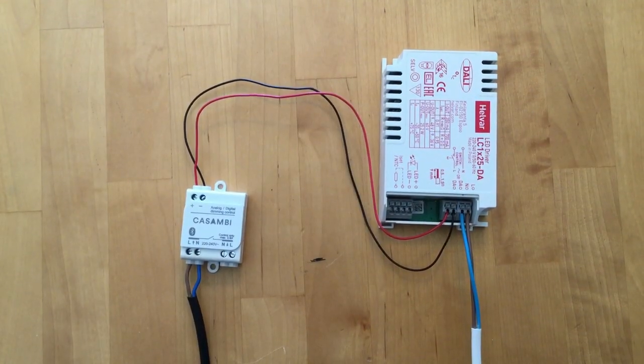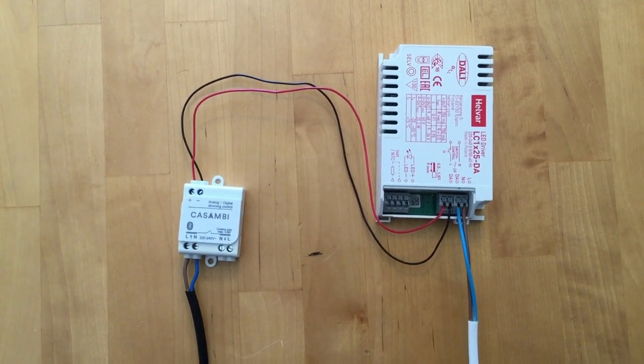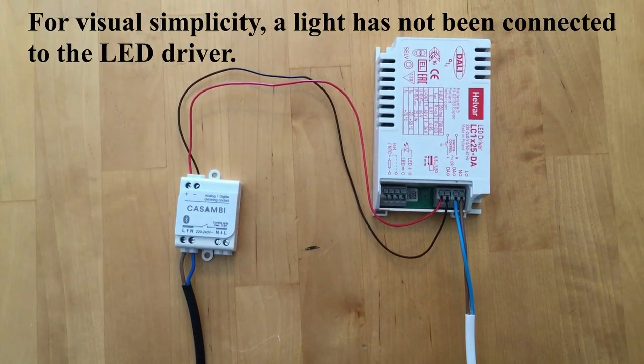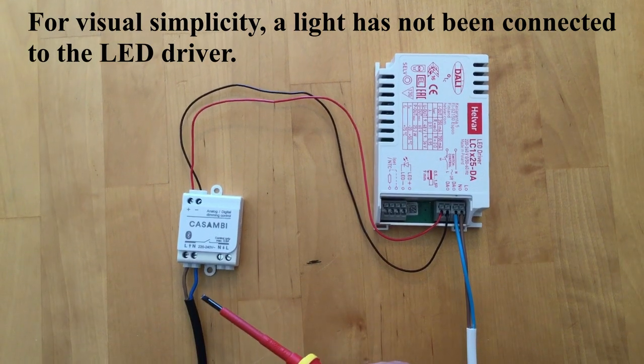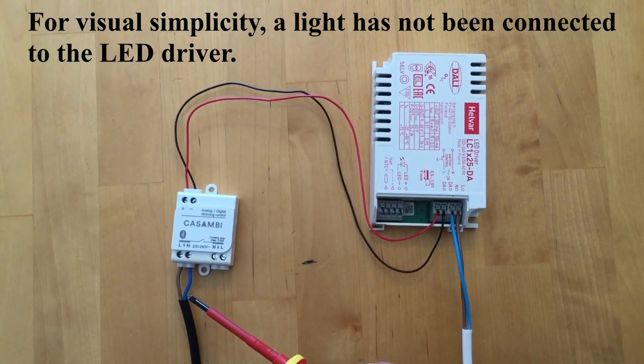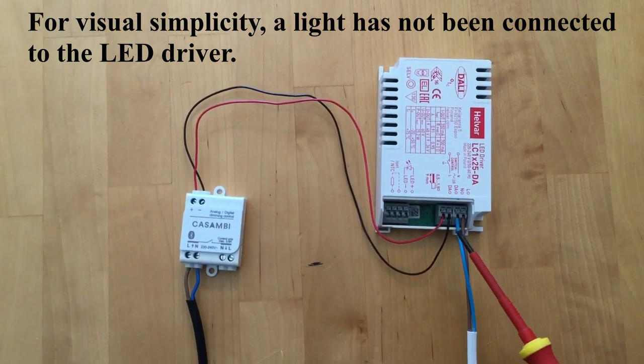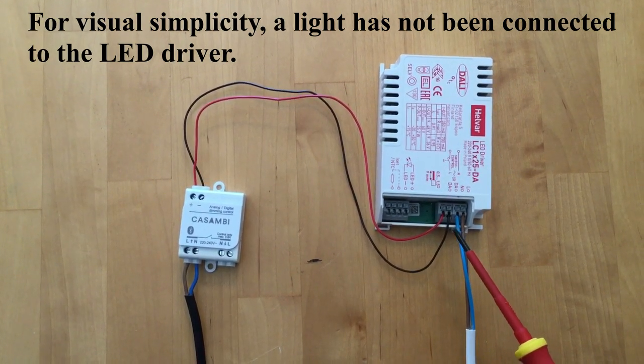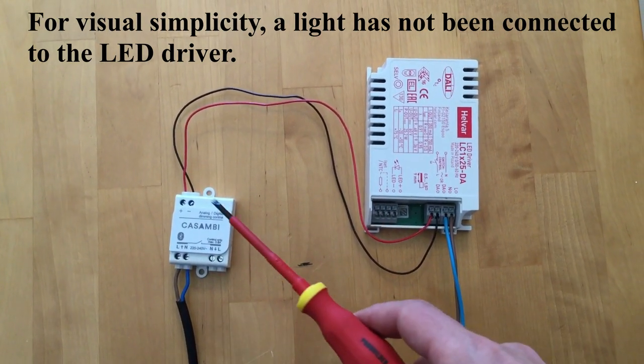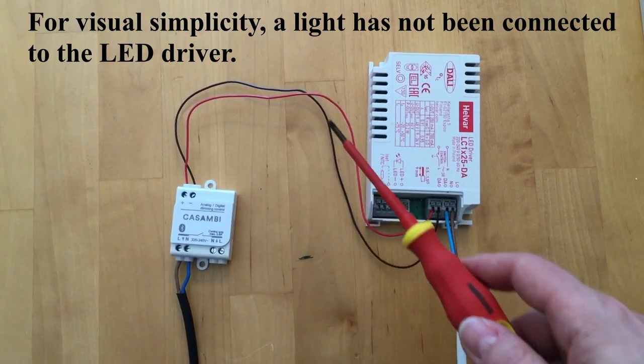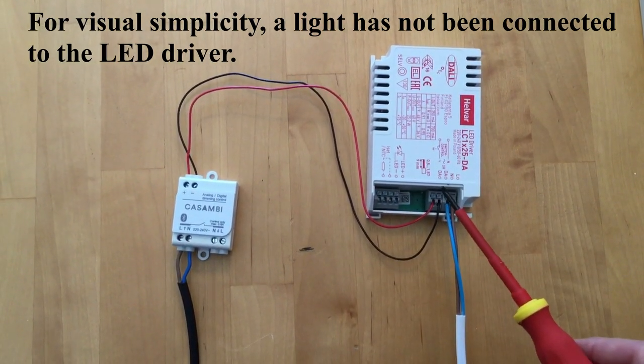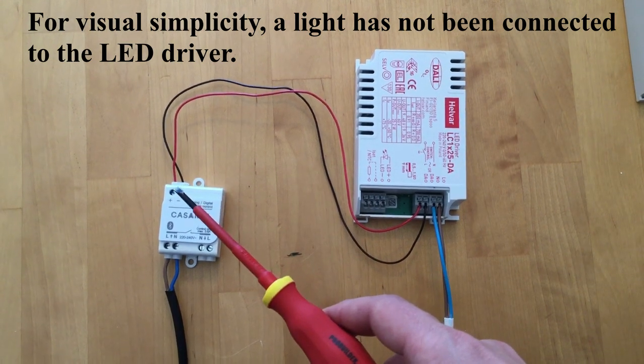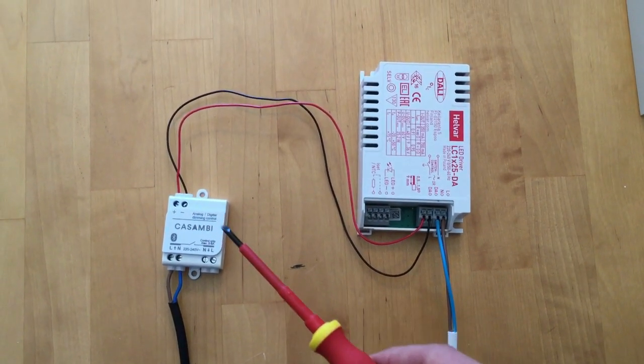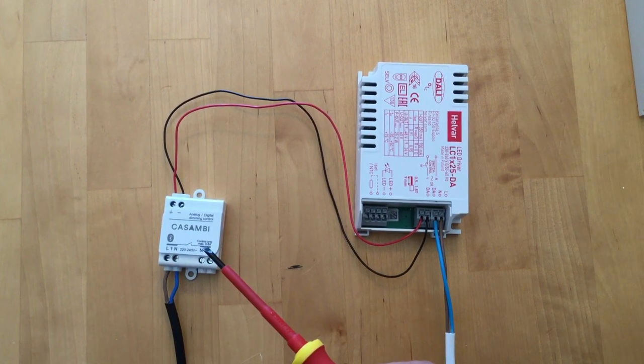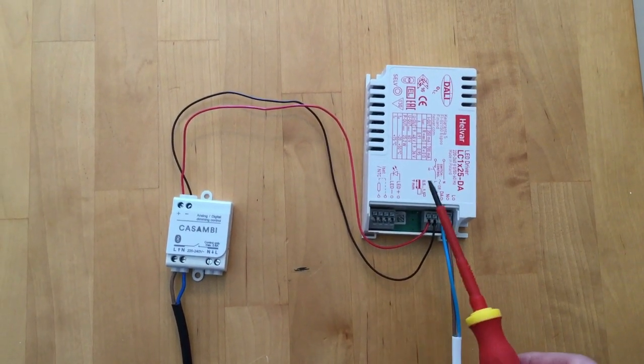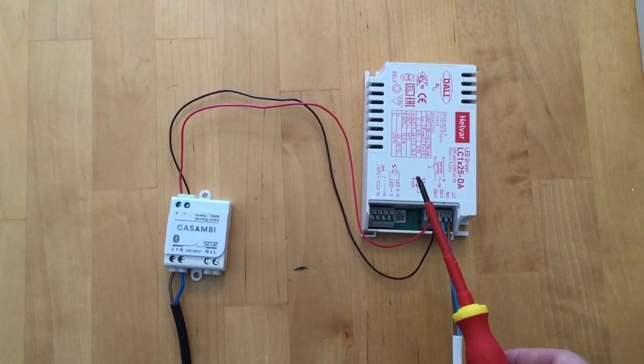This is an example of a DALI driver connected to a CBU-ASD. The CBU-ASD has its own power source, and the DALI driver has its own power source. The DALI commands are then going via the small cables to the DALI port on the driver and on the ASD. The output port of the ASD is not being used to power the LED driver and should not be.